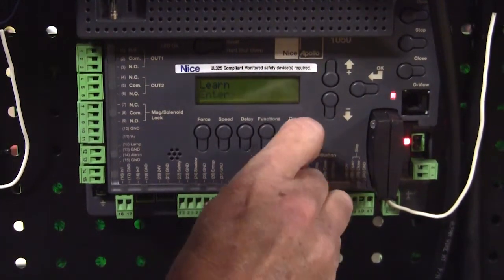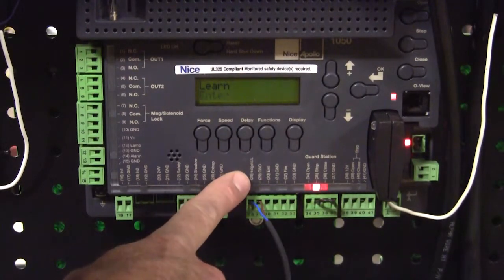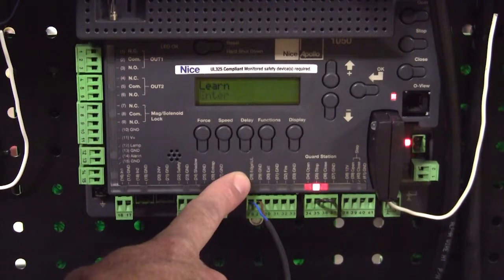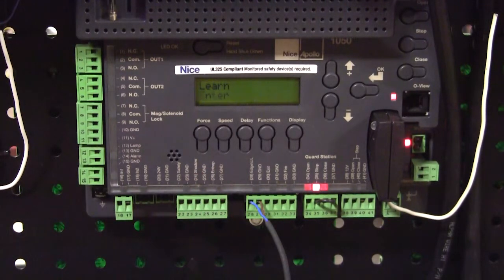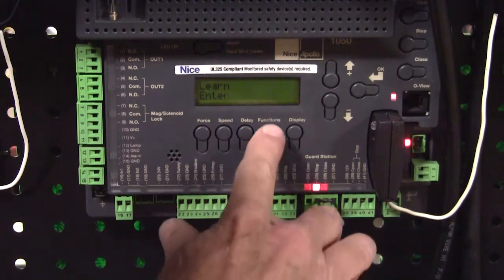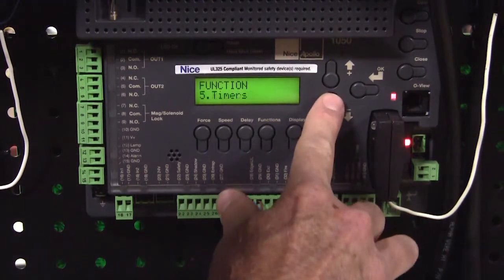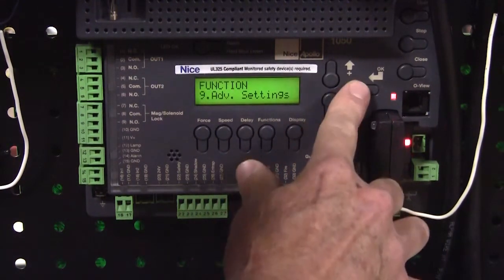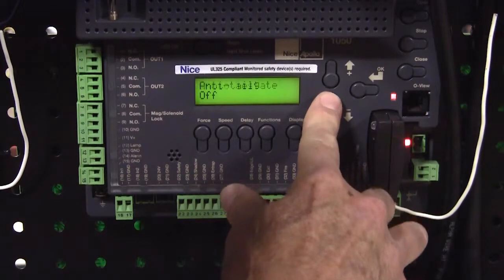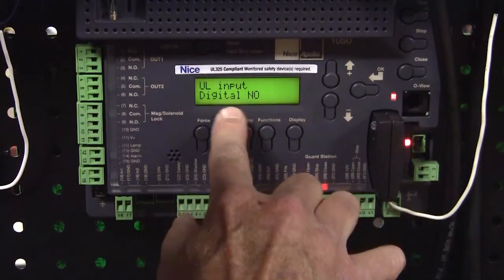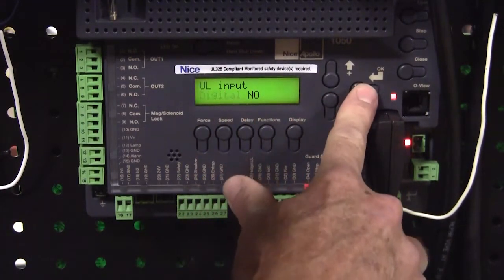Now the UL edge input is defaulted as a digital normally open input. That means it's looking for just a dry contact. So to change this input to a monitored entrapment input we have to go into functions, go down to advanced settings, and let's go down to UL input digital normally open. To change that we press ok.